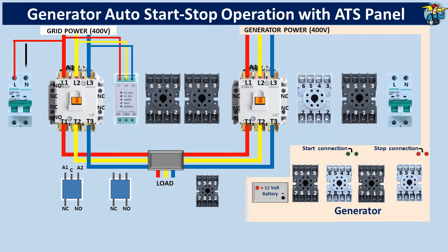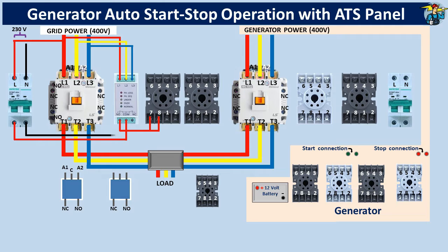Connect a phase line and the neutral line to the 2-pole breaker. From the breaker, the phase line is connected to the common port of the phase failure relay. The normally open port on the left side will connect to terminal number 7 of the grid side, which is timer number 1. Number 7 is connected to the common port number 8. The neutral line is connected to number 2 of timer number 1. Output terminal number 6 goes to the number 7 port of the DPDT relay.